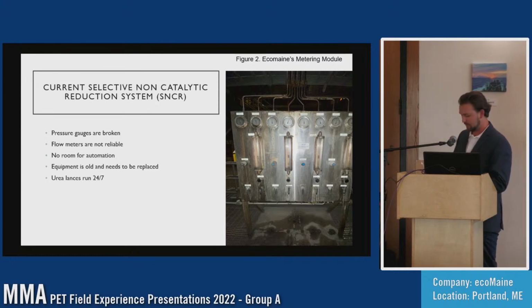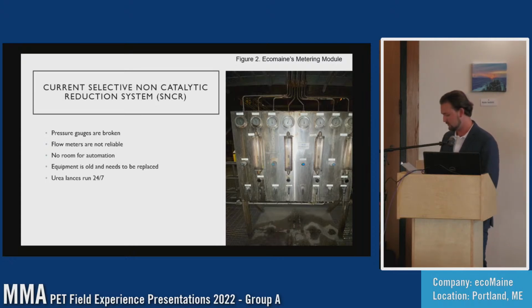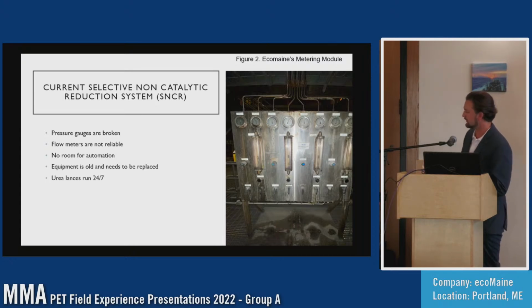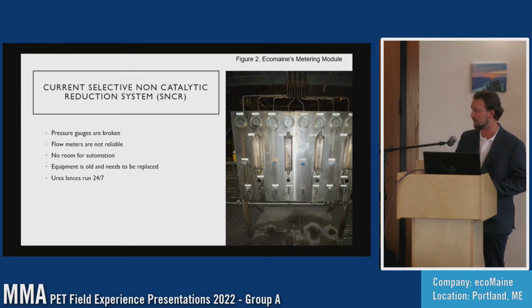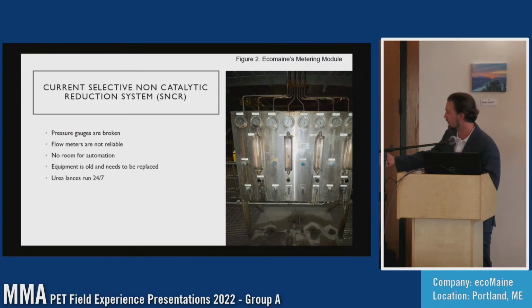The problems that Eco Maine's current system has are that many of the pressure gauges are broken. The flow meters are not reliable. There's no room for automation. The equipment is old and is ready to be upgraded. And lastly, the urea lances run 24/7 when the boilers are online. Those are our flow meters and our pressure gauges right there.